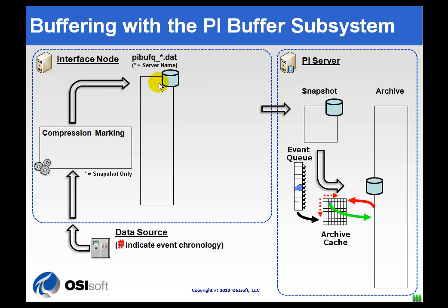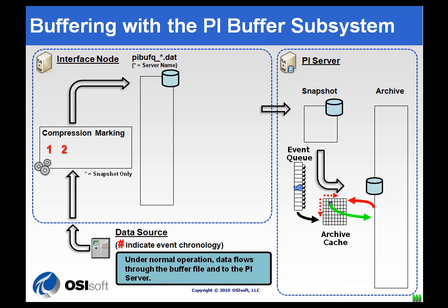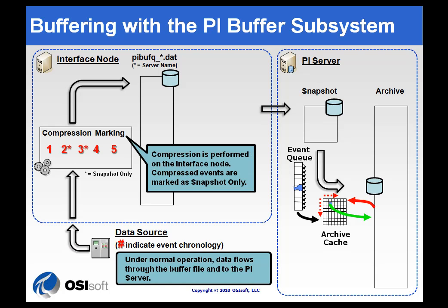It does the compression test on the Interface Node and then sends the data along to the PI Server. It will send it temporarily into a little queue in memory, and if everything is good on that end, it will continue to send. In normal data flow, values come into the system, we do a compression test, and flag which values will fail compression — those with the asterisk are sent as snapshot values but won't make it into the archive. Values that pass the compression test will make it into the archive.